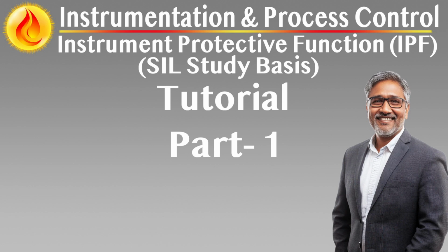Quantitative requirements by SIL level. SIL 1, PFDAVG 10^-1 to 10^-2. Typical risk reduction factor 10 to 100. SIL 2, PFDAVG 10^-2 to 10^-3. Typical risk reduction factor 100 to 1000.